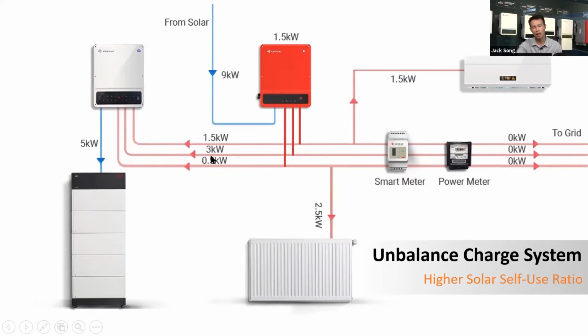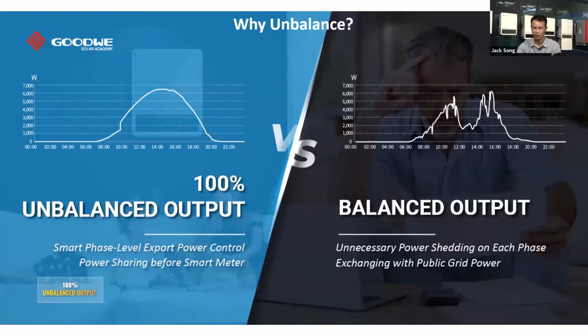So this unbalanced output and unbalanced charge function is very, very useful in scenarios to increase the self-use of solar power, and also to increase the production of the solar power, especially in places with a zero export power limit function. Okay, so till now we have introduced the unbalanced charge and unbalanced outputs, and all these functions are realized in our three-phase energy storage inverters. On-grid inverters cannot realize this. Only storage inverters, coupled or hybrid. Only three-phase energy storage.